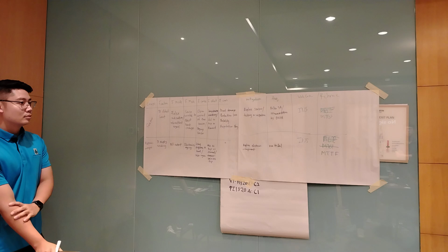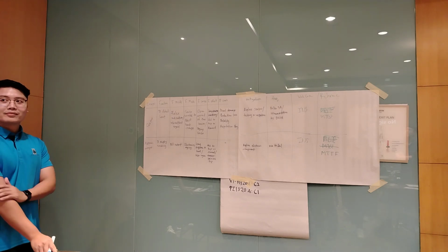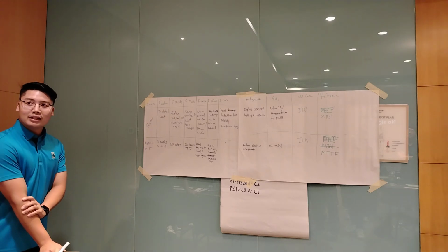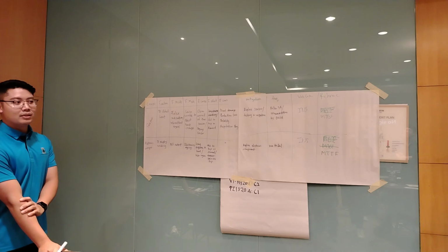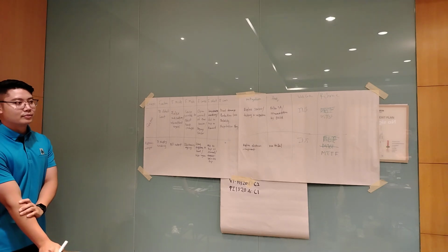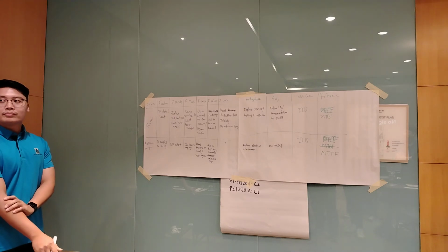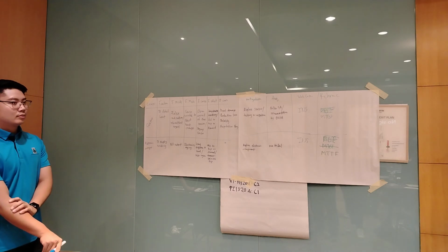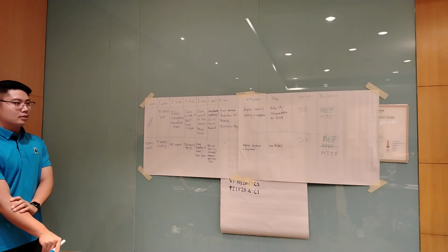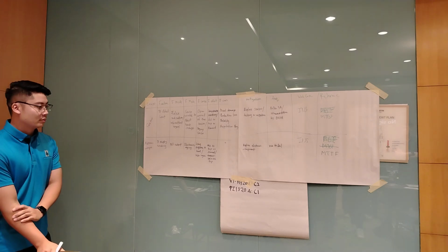But by the time you look at it, it's not blinking, right? You need to say no output lah. But how frequent you check it? Berapa ppm kita bila? 6 months. So you have to go there and check got output, no output, right? Usually our DCS, if there is any alarm or you link to our DCS, you will have a pop-up. I see. Understood. Keep flashing up the alarm. You no need to go physically see whether got light or not lah. No need. Once our DCS detects, then we know what to do.